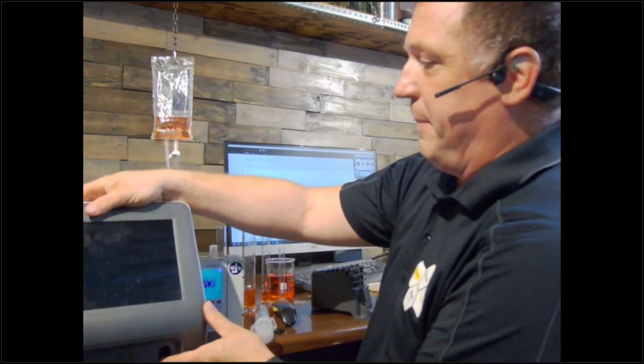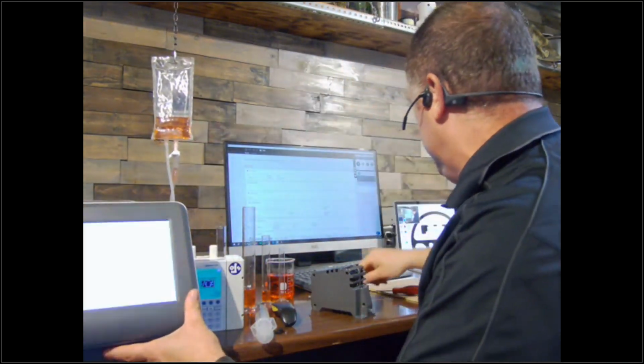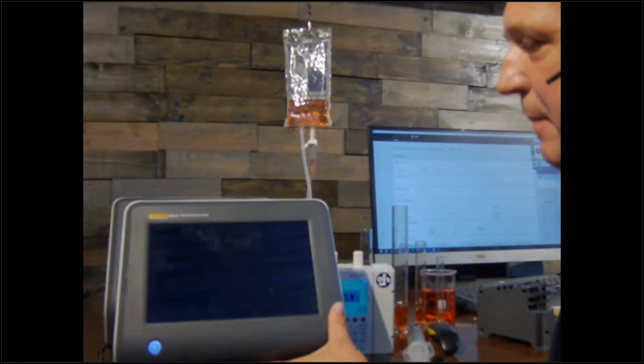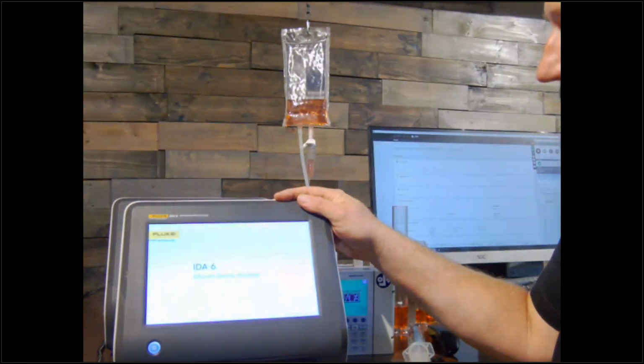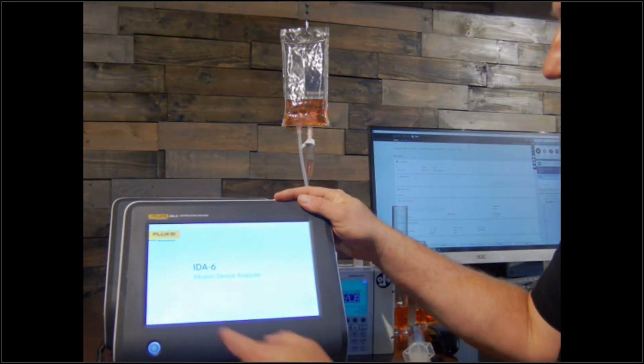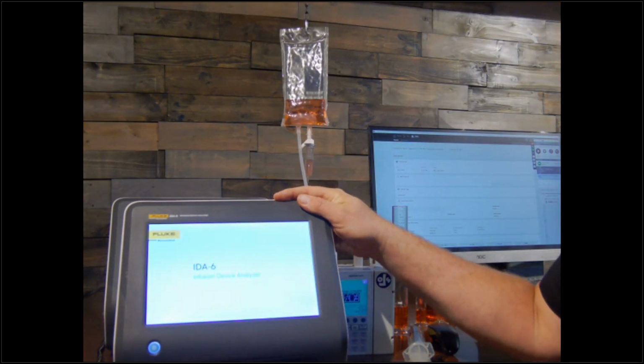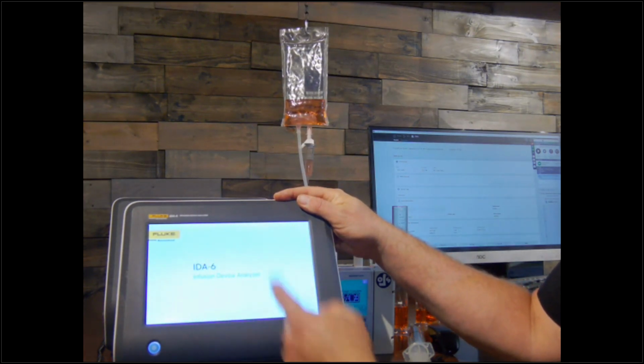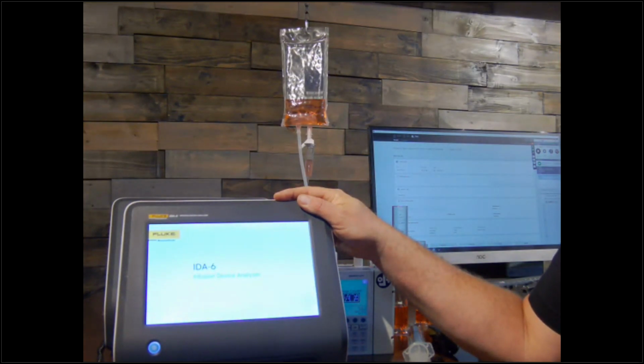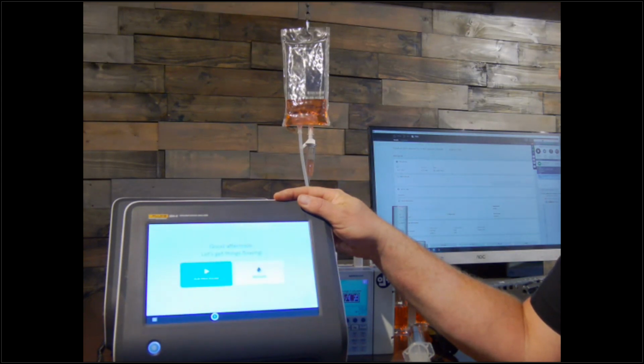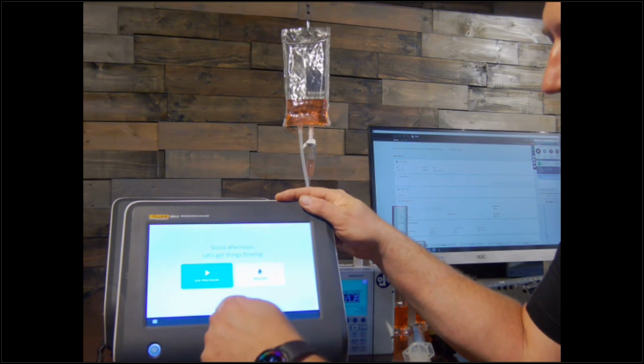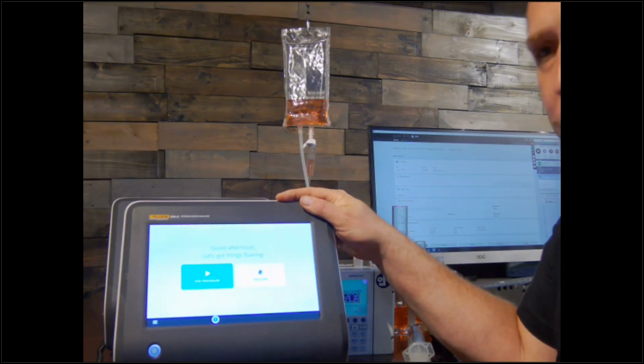Okay, so here we go, we are now missing a channel. All that happens is when you're missing a channel, you power it down, then let me zoom in here. If you have a channel out, as soon as we boot up, on the bottom where it lists all the channels, instead of having a 4-channel or 2-channel unit, I now have a 1-channel IDA-6, and only channel 1 will be highlighted. That's all, you can take channels out or add them, you can buy a 2-channel and add it to make it a 4-channel. See, only channel 1 now, that's all.